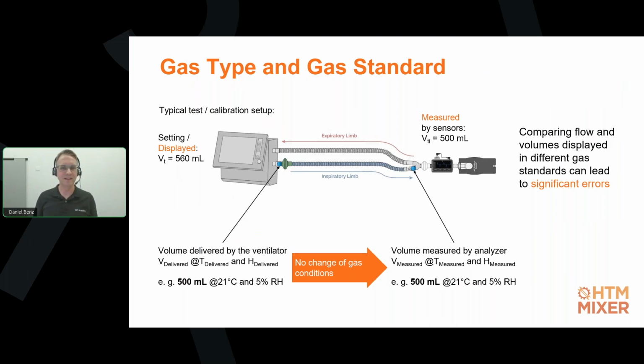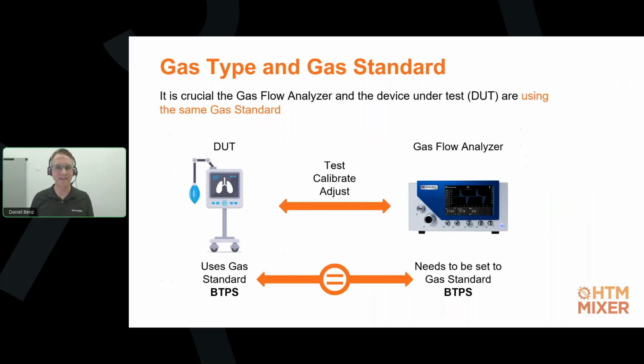And as you can see, this can lead to significant errors. So how do gas flow analyzers tackle this problem? Well, they let you display flow and volume in different gas standards. And the only thing you really need to remember is that the gas standard setting on your gas flow analyzer must always match the gas standard used by the device under test, typically your ventilator or anesthesia machine.